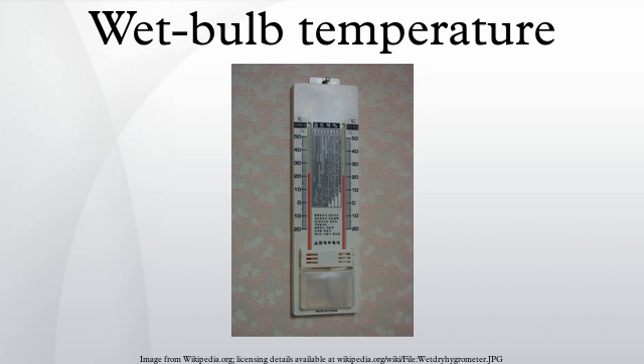For dry air — air that is less than saturated — the wet bulb temperature is lower than the dry bulb temperature due to evaporative cooling. The greater the difference between the wet and dry bulb temperatures, the drier the air and the lower the relative humidity. The dew point temperature is the temperature at which the ambient air must cool to reach 100% relative humidity, where condensate and rain form. Conversely, the wet bulb temperature rises to converge on the dry bulb temperature.